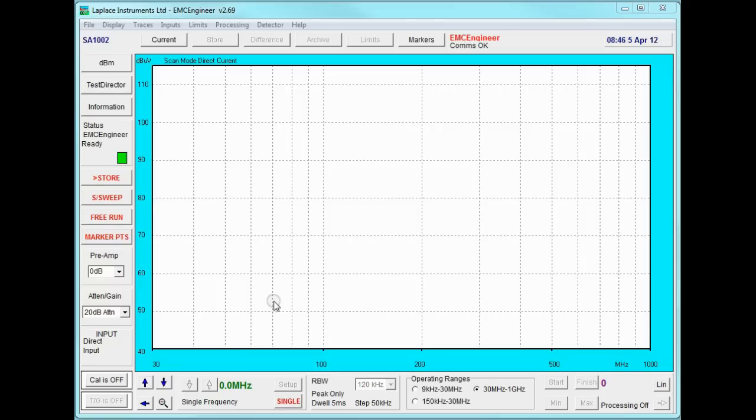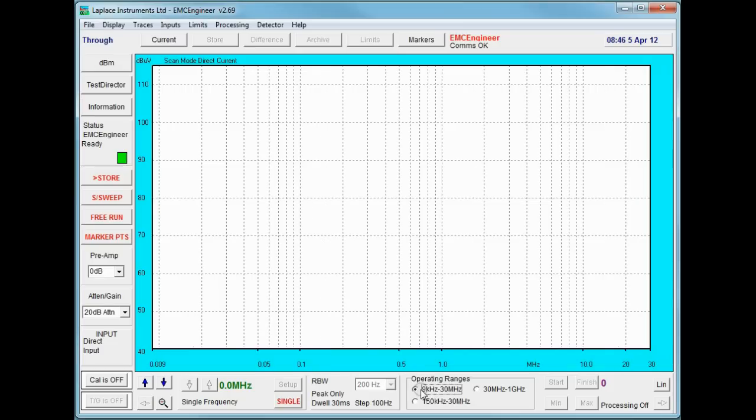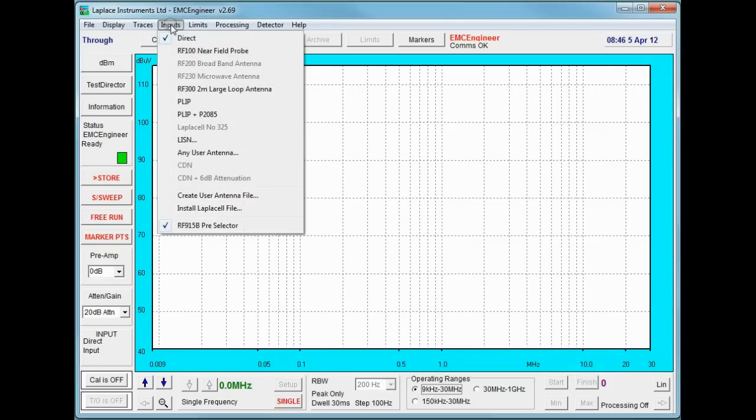First thing we need to do is to set the frequency range of interest, which is 9 kHz to 30 MHz, and set the input device, which in this case is going to be the LISN.